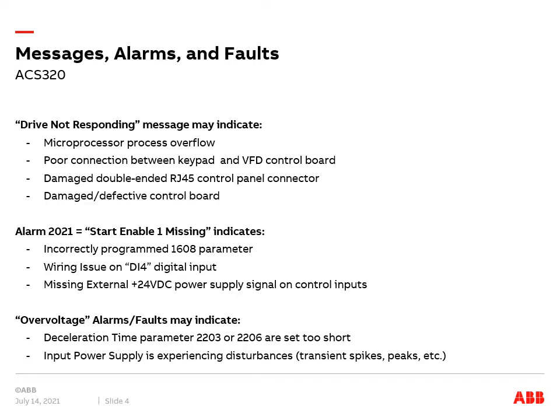Setting parameter 1608 equal to not used, or wiring the control input, will clear alarm 2021.